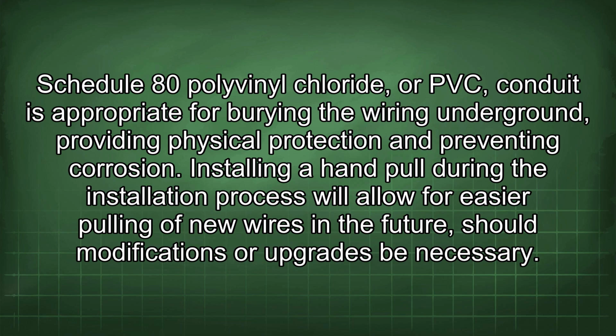Schedule 80 polyvinyl chloride, or PVC conduit is appropriate for burying the wiring underground, providing physical protection and preventing corrosion. Installing a hand pull during the installation process will allow for easier pulling of new wires in the future should modifications or upgrades be necessary.